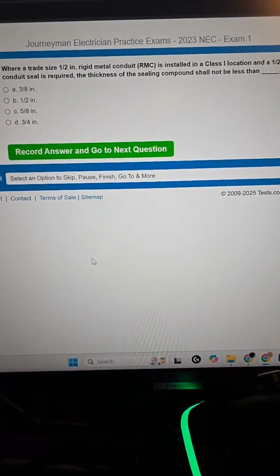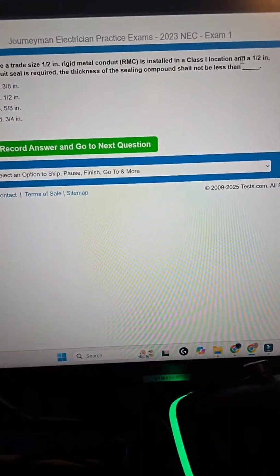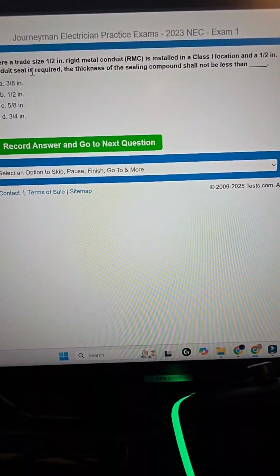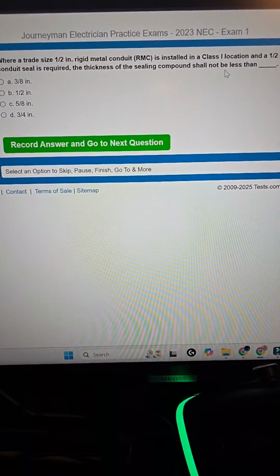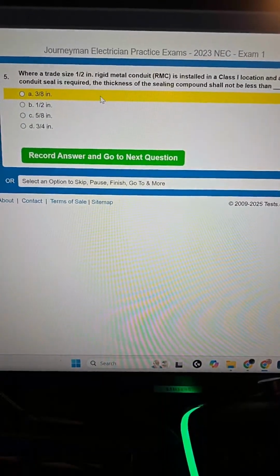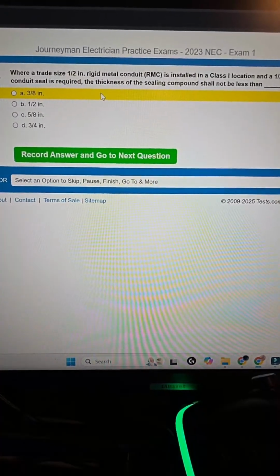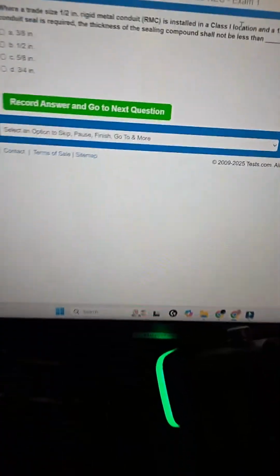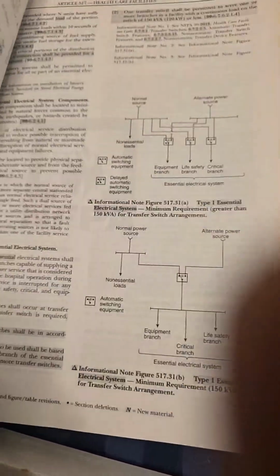Let's go. For trade size 1/2-inch RMC is in a class 1 location and 1/2-inch conduit seal is required. The thickness of the sealing compound should not be less than. This is a very cool question for a master's test, actually. So let's go look at class 1 locations, which is going to be in Article 500. And it's going to talk about the class of locations. So we're in classified locations. And we know that we're looking at a class 1 location. There's our classes there. So we're going to keep going.